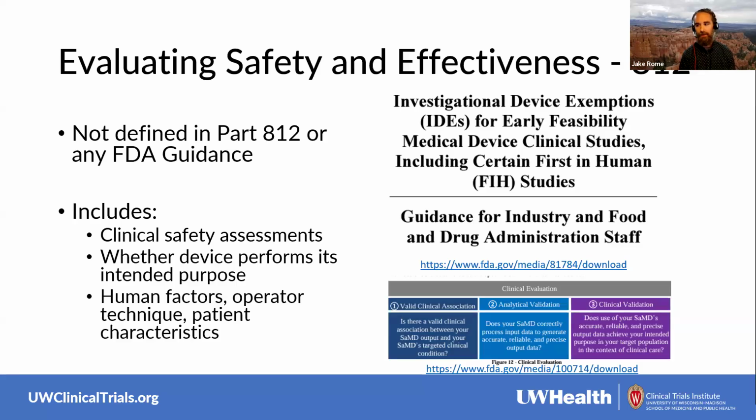So an example of that would be using software to collect data for a drug study or surgical intervention, or maybe you have some investigational software that you're going to run some imaging on to help with some of your study aims, but you're not looking to evaluate how well the software works. Even if that software isn't FDA approved, it might fall outside of the scope of 812 requirements. That changes if you want to evaluate how effective the software is as an exploratory aim of your study. In that case, you're bringing your whole study into FDA regulation.